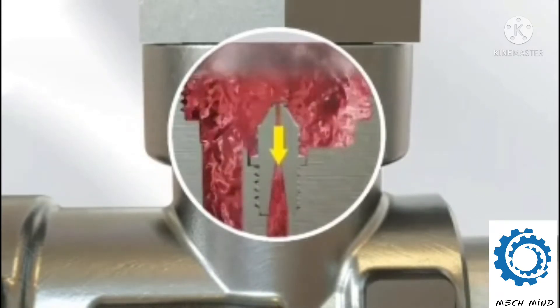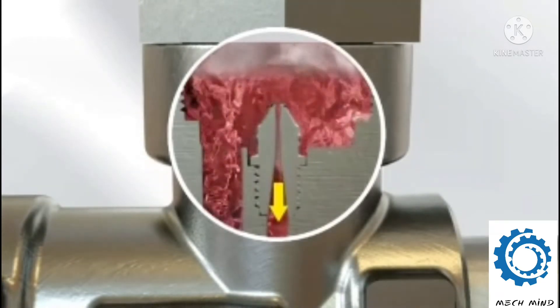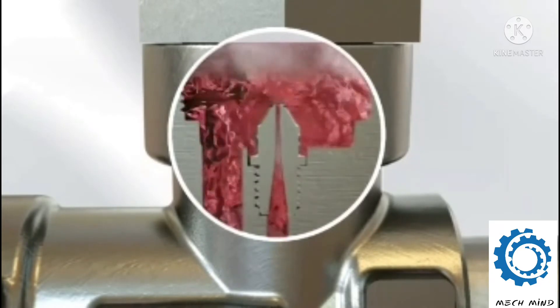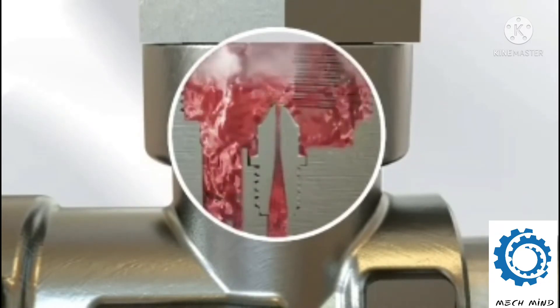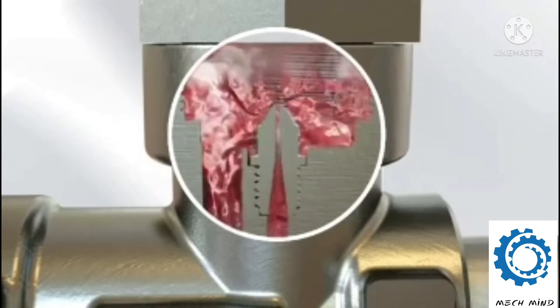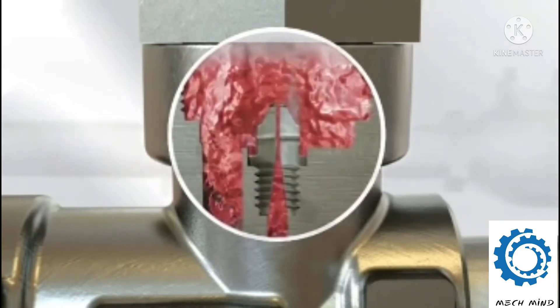This flashing creates a back pressure zone in the mouth of the venturi. Because condensate is one thousand times denser than steam, it is able to push through this back pressure zone while restricting the steam.